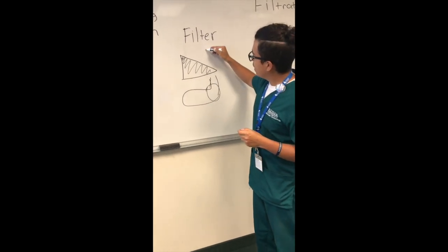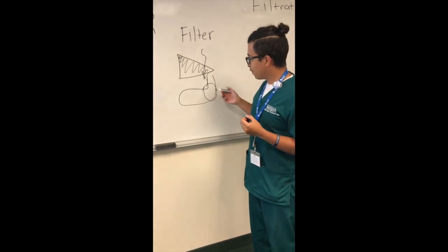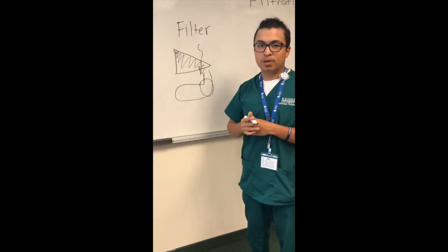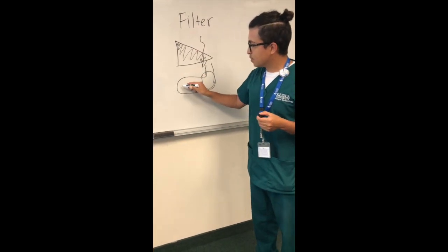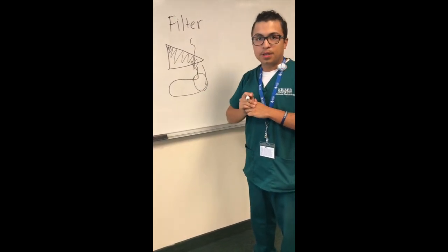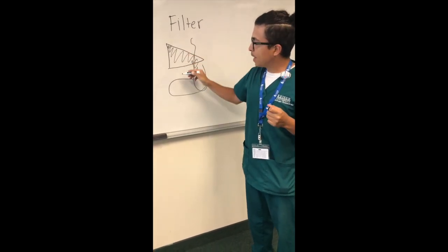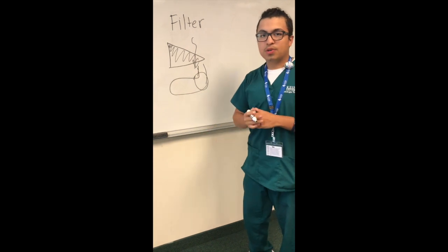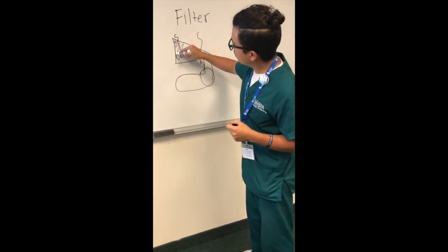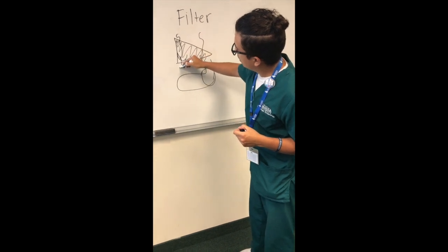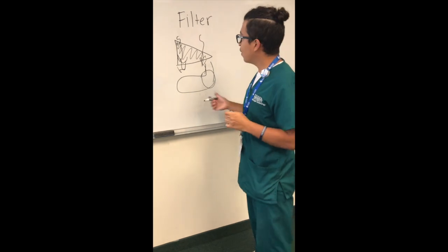So we would need the X-ray photons to travel easily through the filter, so it's able to provide better penetration and show a clear image on the X-ray. And on this side, since towards the phalanges or the toes, we would need more stopping power. Otherwise, it would over-penetrate the image and you wouldn't get a clear image. So the X-rays are traveling through here, and they're stopped more than they would on this side, just to even out the amount of power.